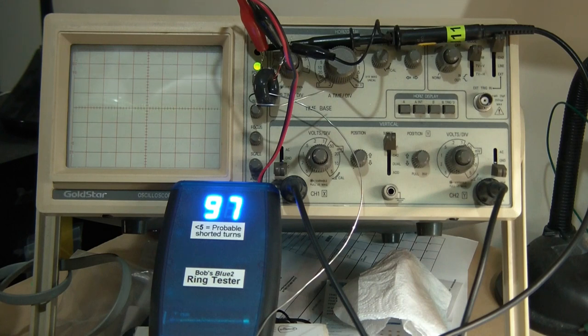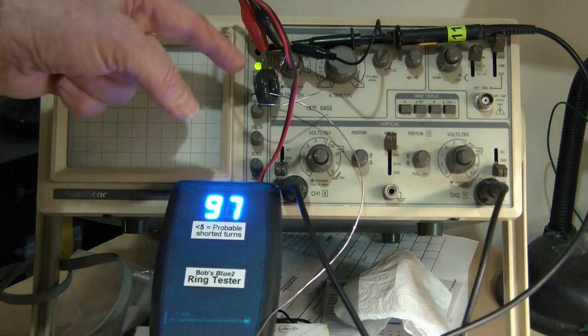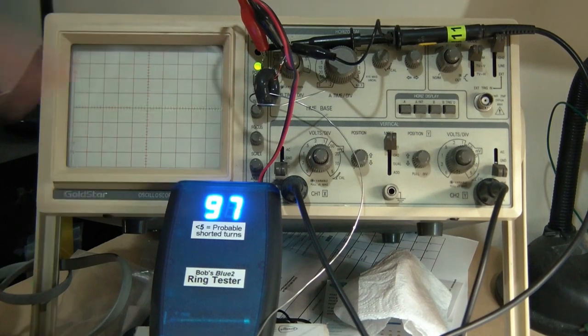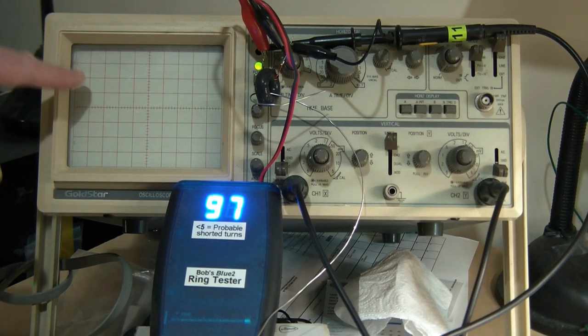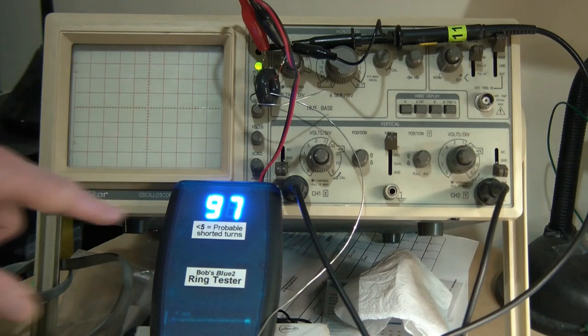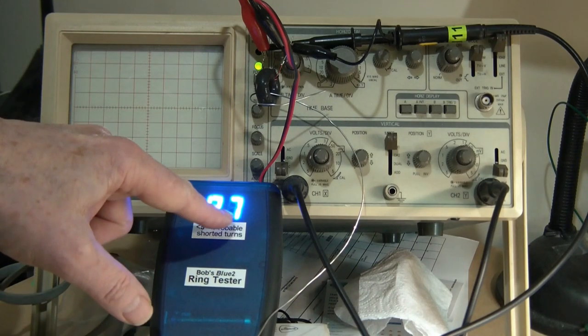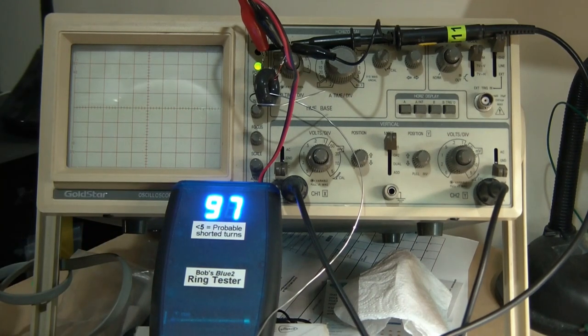At the moment it is ring testing this little toroid here, which came out of a power supply. And you can see that it is ringing. The counter says it's 97 times it's ringing.